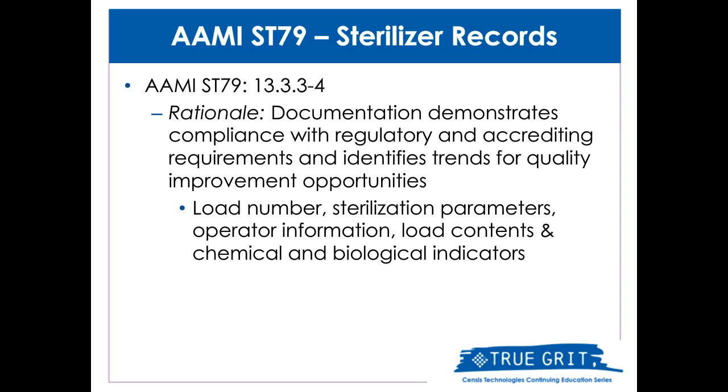Why does AAMI make the recommendation for the use of an electronic tracking system? The rationale is the ability to demonstrate compliance and identify trends for quality improvement — it's all about patient safety. For each sterilization load, the following information should be recorded: the load number; the specific content of the load or lot, including the quantity, the department, and a specific description of the items such as towel packs or instrument set names; the exposure time and temperature if not on the sterilization recording chart; operator identification; the results of biological testing and Bowie-Dick testing if applicable; the response of chemical indicator placed in the PCD if applicable; and any reports of inconclusive or non-responsive CIs found later in the process.